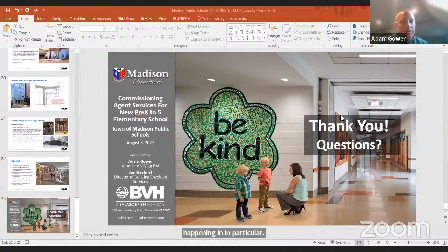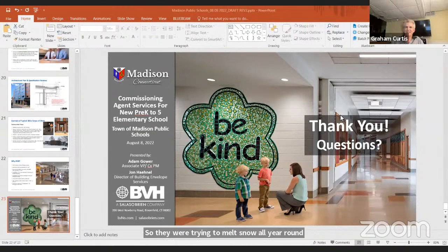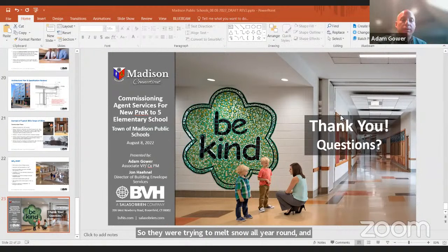I've got a story for you. We did this for a community college in Connecticut. During the warranty review, we didn't do measurement and verification, but reviewing the trends, we noticed high gas consumption compared to the energy model. We drilled down deeper to find the root cause. The building facilities staff had overridden the snow melt to be on all the time and enabled the boilers to come on all the time as well. They were trying to melt snow all year round and just burning gas. That was one thing we found from that aspect.